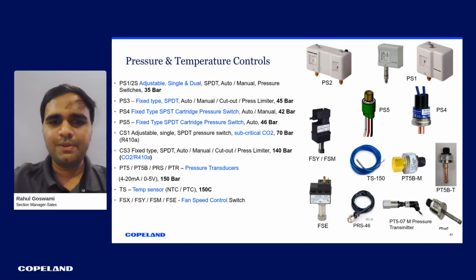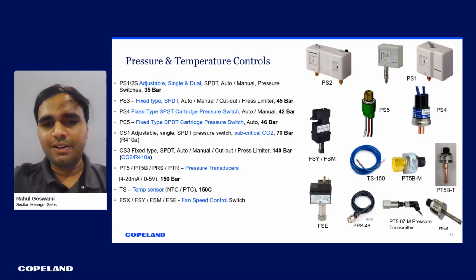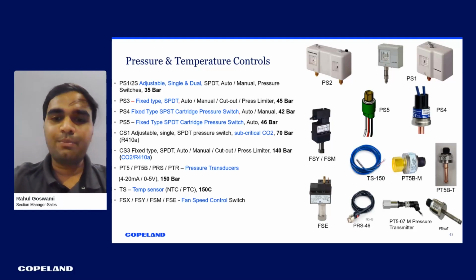Again, it is SPDT. Then we have a PS4, which is SPST. It is a cartridge type pressure switch, and it can cover up to 42 bar. We have the PS5 series, which is SPDT cartridge type, which can cover up to 46 bar. We have a pressure control solution even for subcritical applications like CO2, which can cover up to a maximum of 70 bar. Then if you have any requirement up to 140 bar, again there are solutions available with us by CS3 solutions.